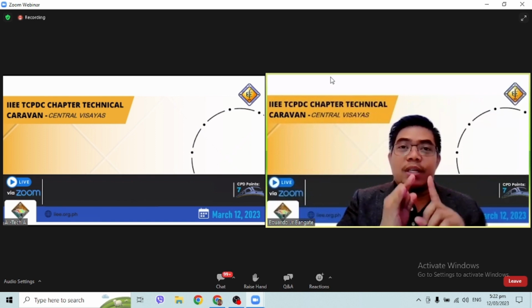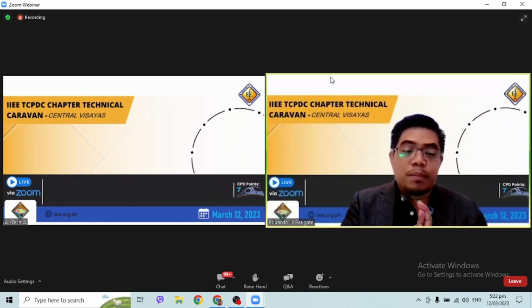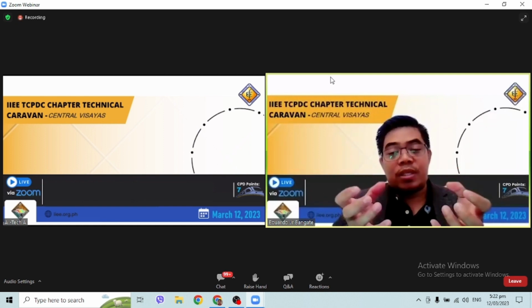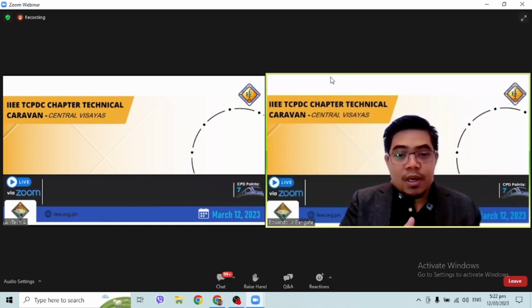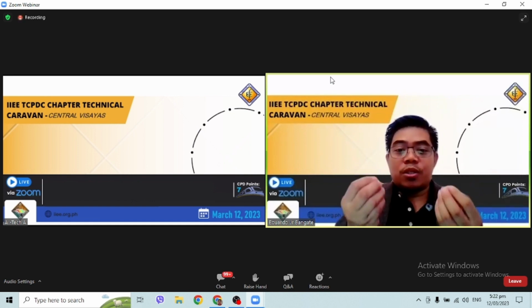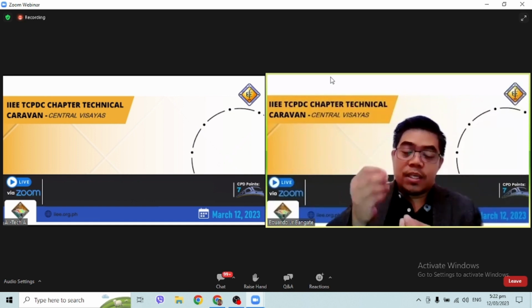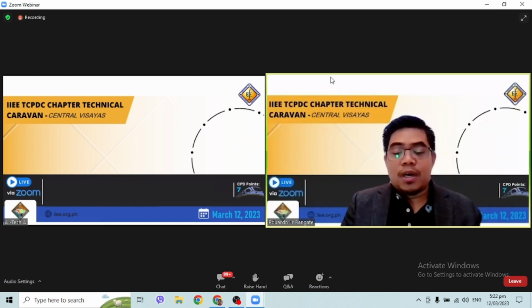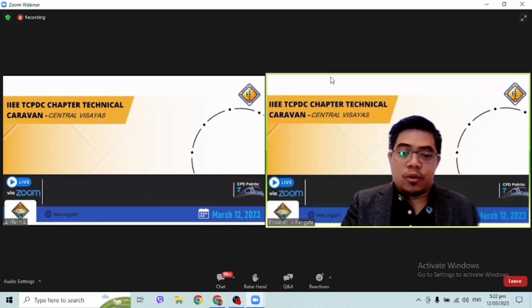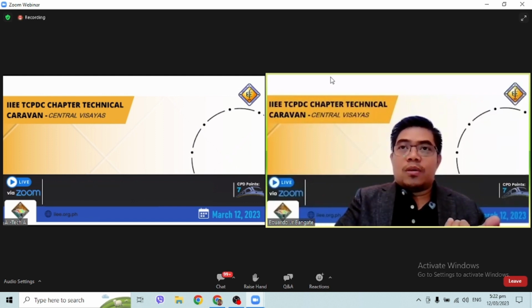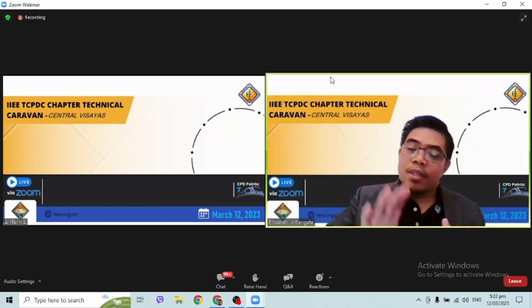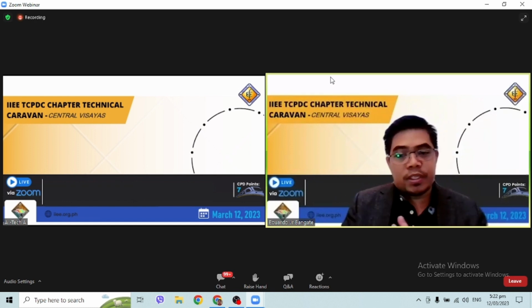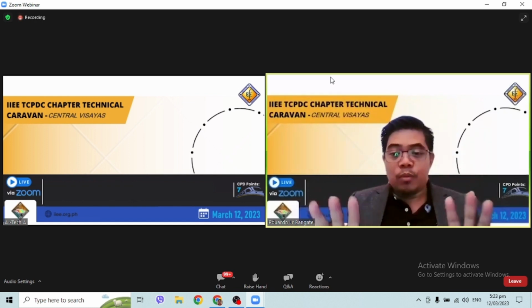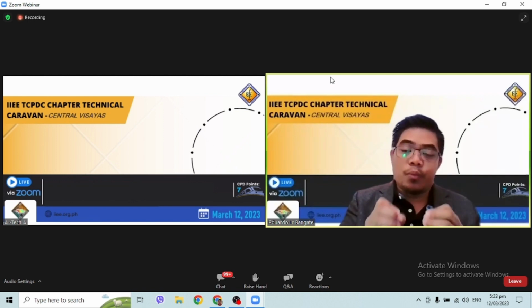And the consequence is the engine will not burn the fuel completely. Doon magbi-build up yung carbon sa ating combustion system. Kapag nag-build up ang carbon doon, it will cause scratches against the cylinder wall. And this will affect the efficiency of our engine and eventually the generator. So, it is important to test with the load bank because we need to make sure that the generator is capable, but at the same time, everybody must understand that the operating level of the generator should be around 70 to 80%. That is the optimum level, the perfect condition for every generator to work.